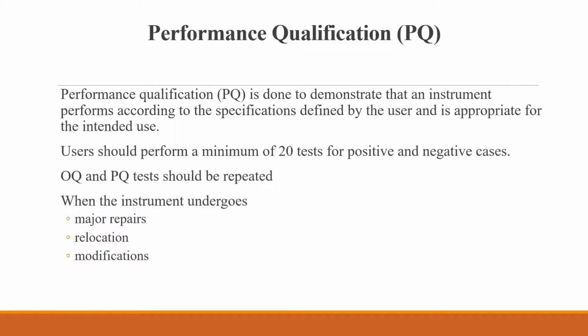After you perform the IQ and OQ, you now have to do the PQ, performance qualification. When do you do this? It's done to demonstrate that an instrument performs according to the specifications defined by the user and is appropriate for intended use. Let's go back again with the refrigerator.